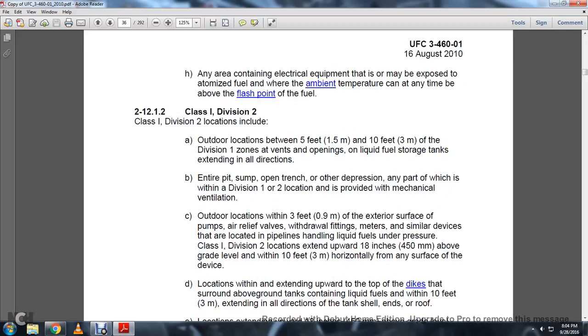2-12.1.2 Class 1 Division 2. Class 1 Division 2 includes locations between 5 to 10 feet beyond the Division 1 zones at vents of open liquid fuel storage tanks, extending in all directions; an entire pit or open trench or depression, any part of which is within Division 1 or 2 locations, provided with mechanical ventilation; outdoor locations within 3 feet of exterior surfaces of pipe, air relief valves, withdrawal fittings, meters, and similar devices located within pipelines handling liquid fuels under pressure. Class 1 Division 2 extends upward 18 inches above grade level and within 10 feet horizontally of any surface of the device.